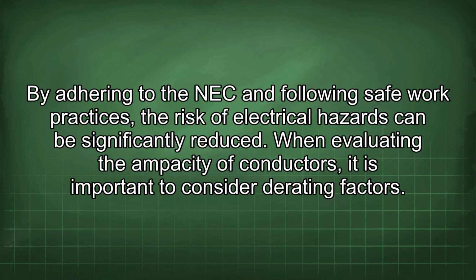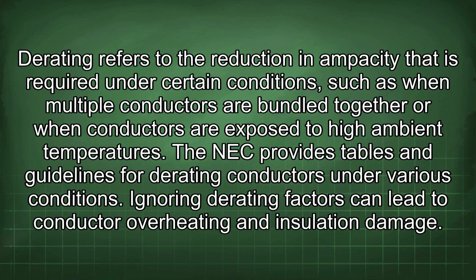When evaluating the ampacity of conductors, it is important to consider derating factors. Derating refers to the reduction in ampacity that is required under certain conditions, such as when multiple conductors are bundled together or when conductors are exposed to high ambient temperatures.